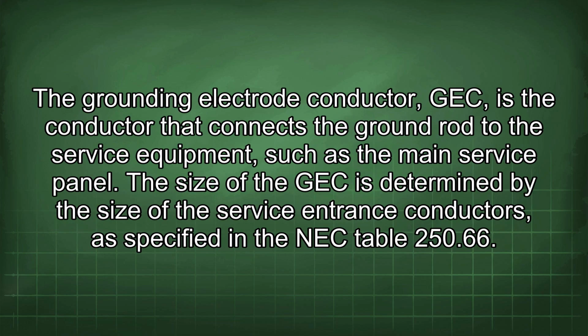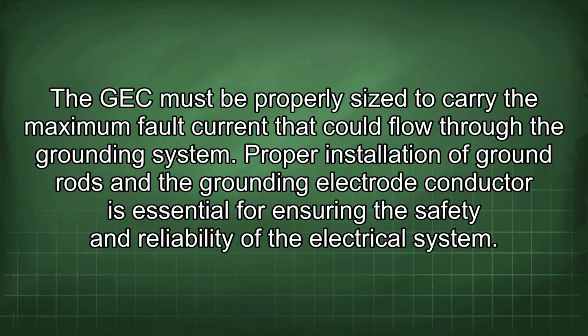The grounding electrode conductor, GEC, is the conductor that connects the ground rod to the service equipment, such as the main service panel. The size of the GEC is determined by the size of the service entrance conductors, as specified in the NEC Table 250.66. The GEC must be properly sized to carry the maximum fault current that could flow through the grounding system.